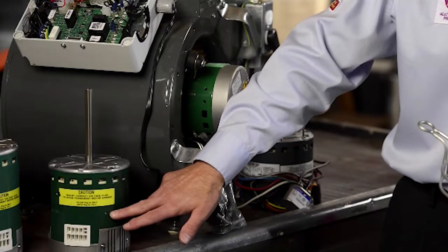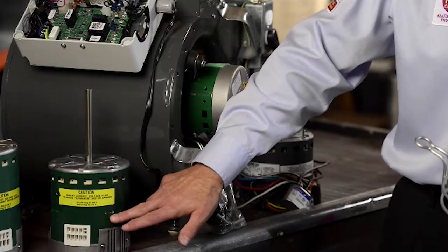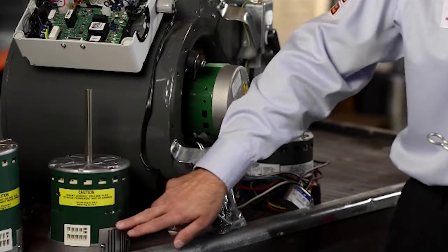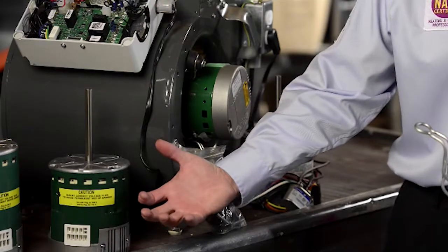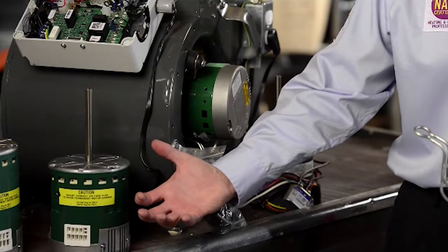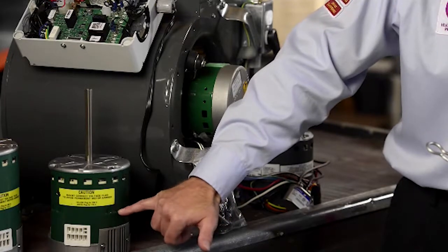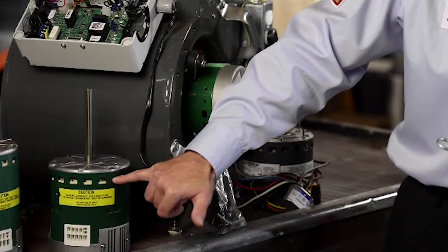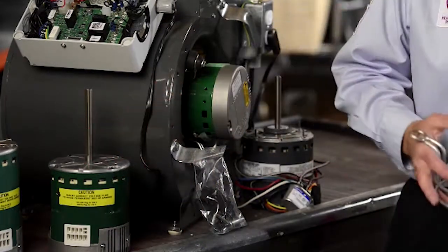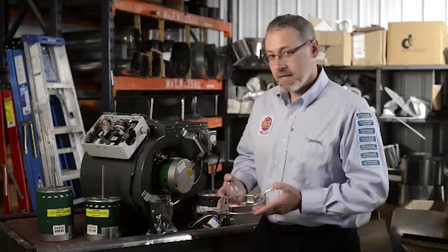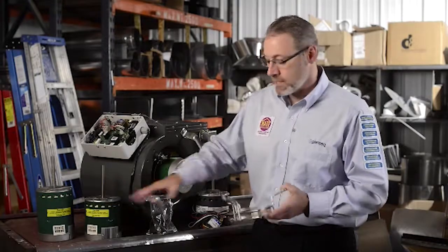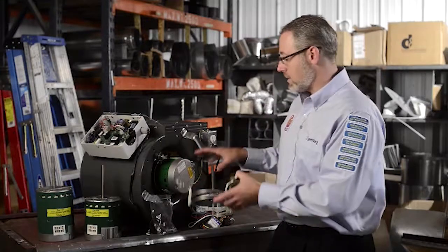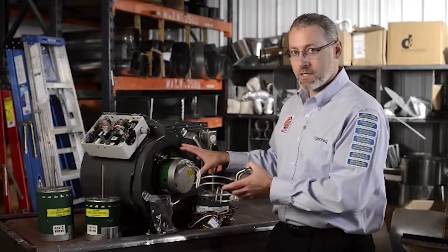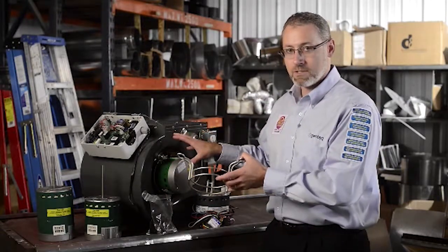These dimples locate the bottom of the stator stack, meaning that below the dimples is the open area in the motor shell where the electronics portion of the motor exists. So we want to keep the motor mount between the dimples and the motor vents, of course not covering the motor vents. Last but not least, to orient the motor in the motor mount, we want to imagine how that motor is going to sit when it exists in the HVAC system.